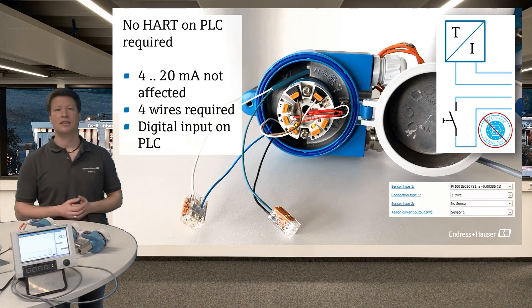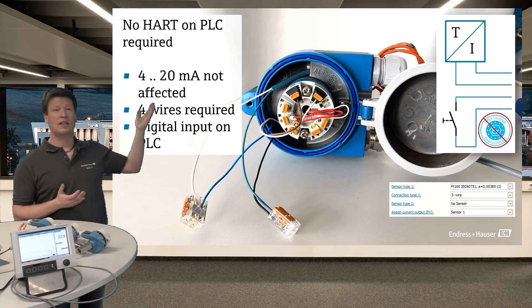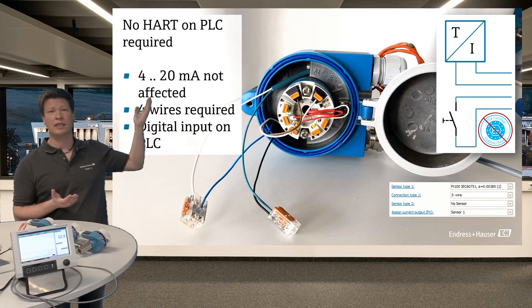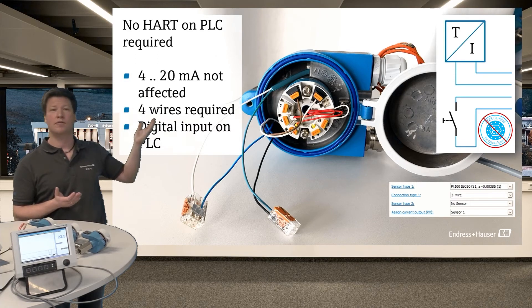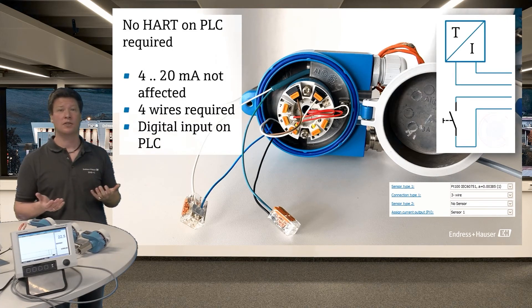Benefits in this case means that no HART signal needs to be detected on the PLC. We still have the temperature signal, 4 to 20 milliamp loop is not affected, but you need four wires to the transmitter. And then you have a digital signal on the PLC to evaluate the error.